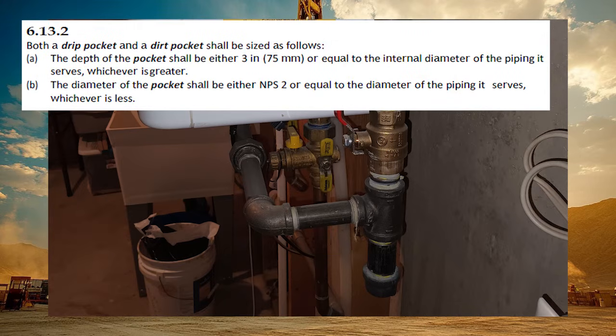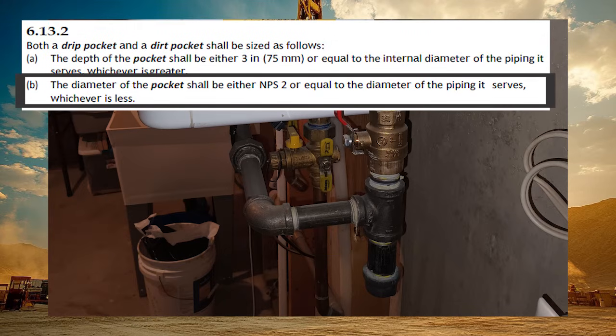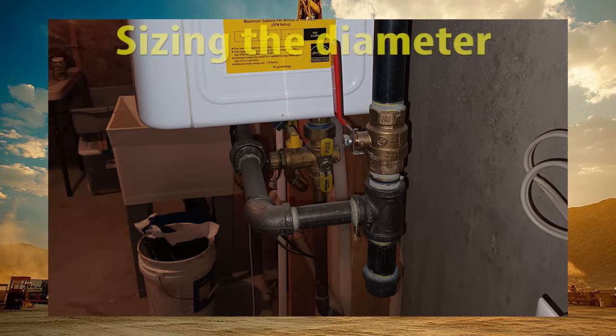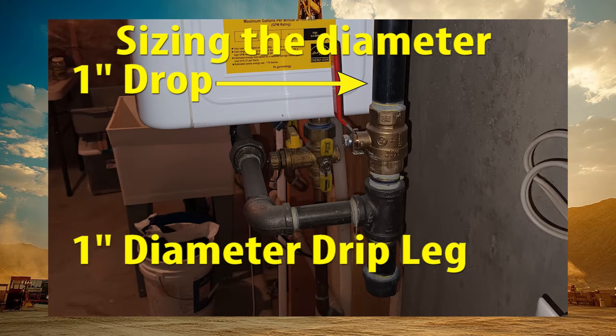Part B of Clause 6.13.2 states, the diameter of the pocket shall be either NPS 2 or equal to the diameter of the piping it serves, whichever is less. This clause is solely referring to sizing the diameter of the dirt pocket. You are supposed to match the size of the drop coming down. So if I have a 1-inch drop coming down to serve an appliance, I need a 1-inch dirt pocket.